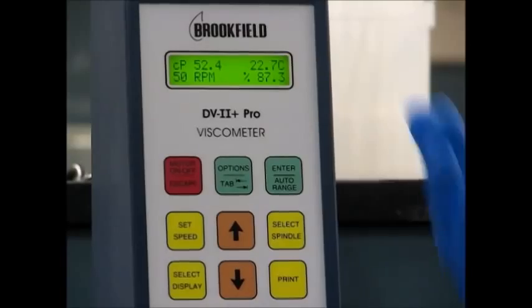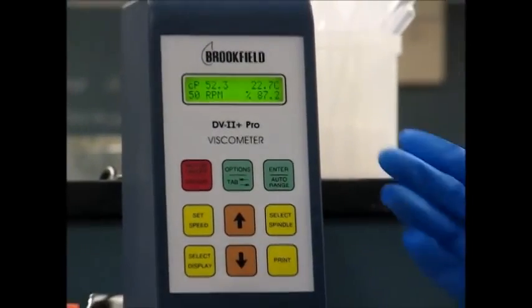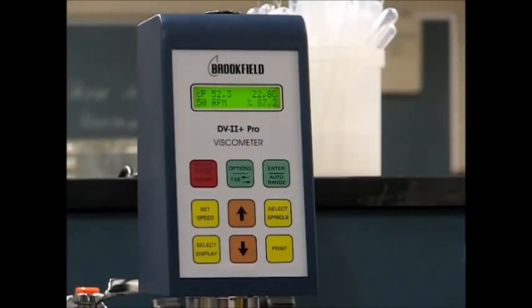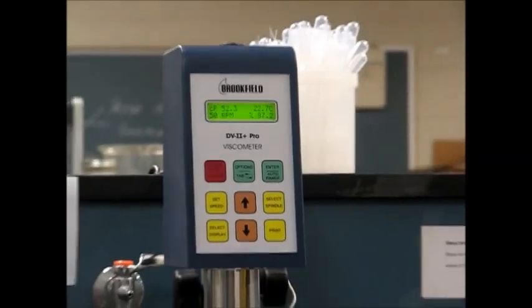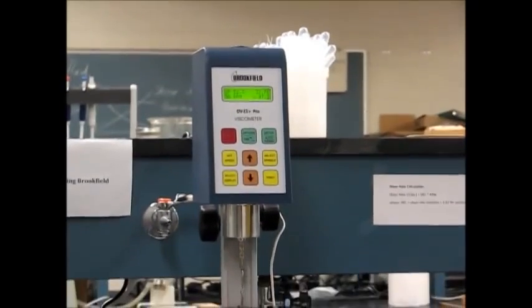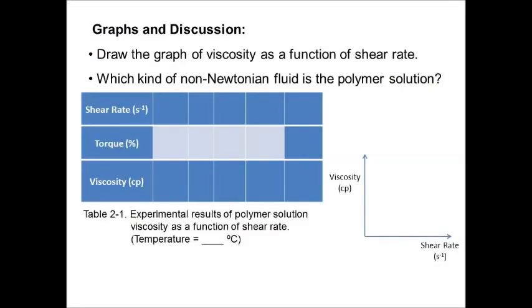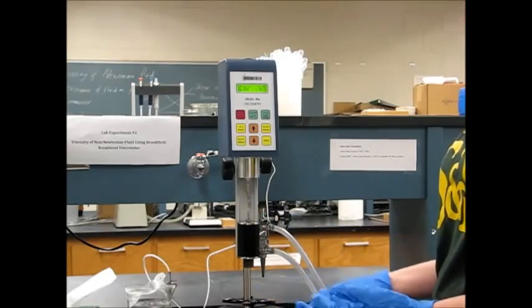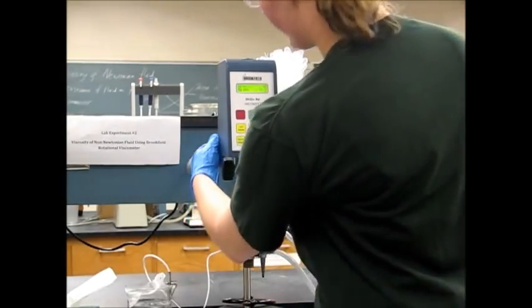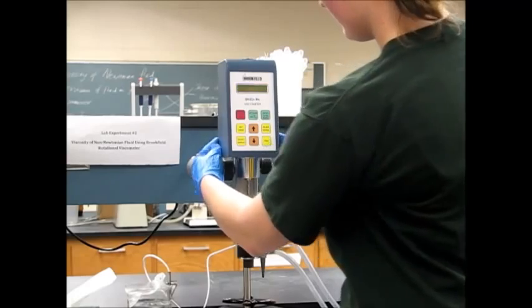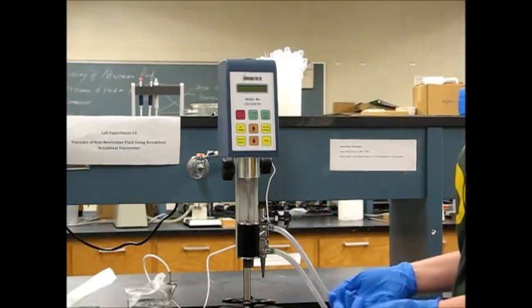Before recording each of your measurements, be sure that the reading on the viscometer has stabilized to ensure accuracy. Also, when you're plotting your shear stress versus viscosity, we need to get these points and find this relationship to determine what kind of fluid we actually have here. When we're finished taking our readings, then we're going to turn off the viscometer, undo everything, and then clean it thoroughly.